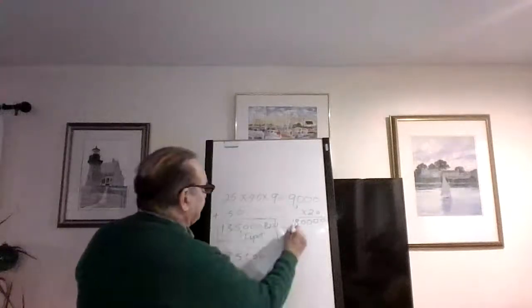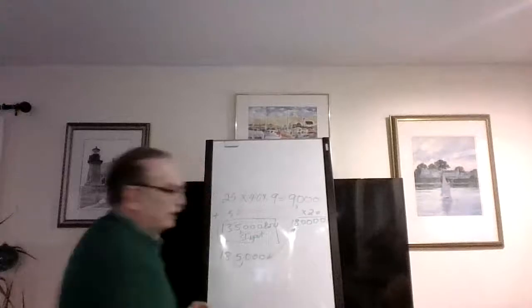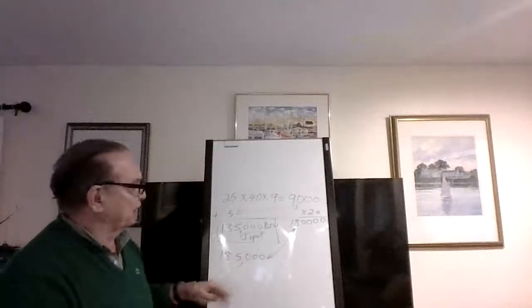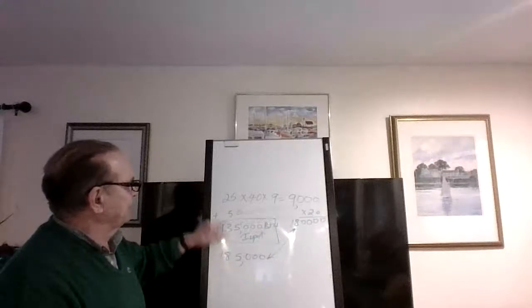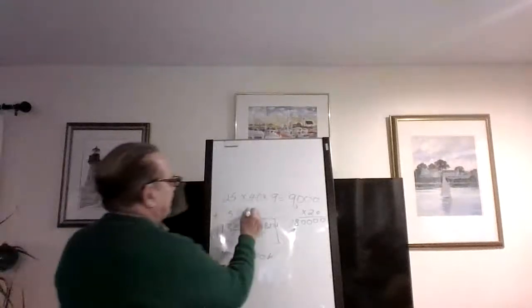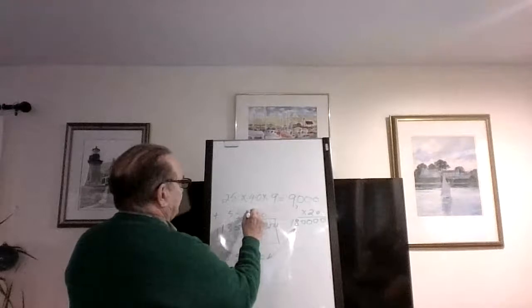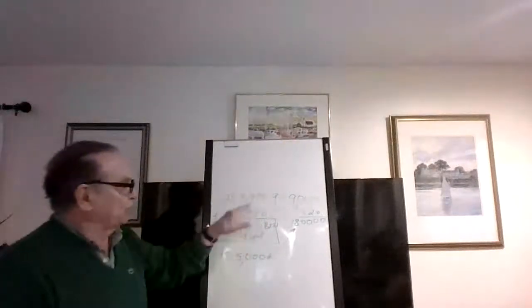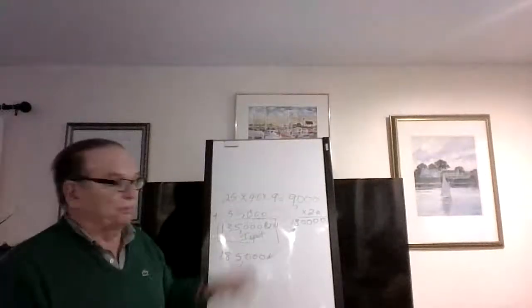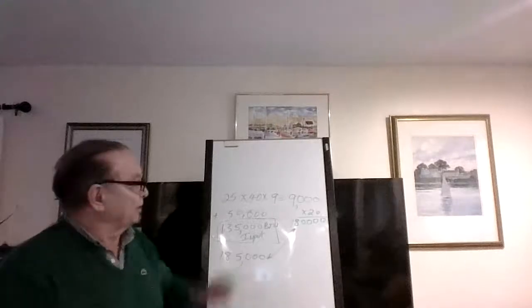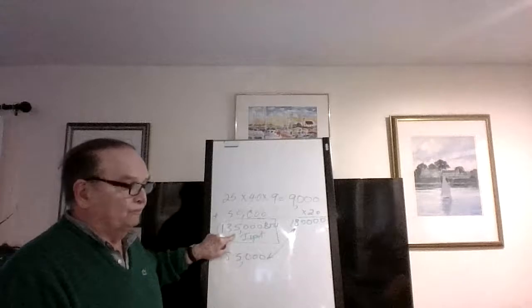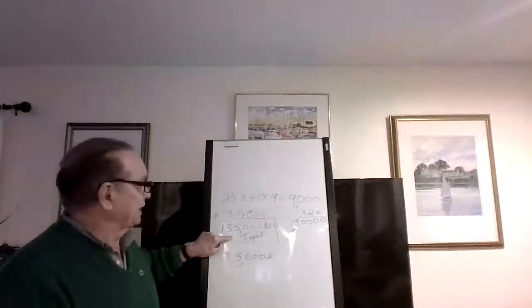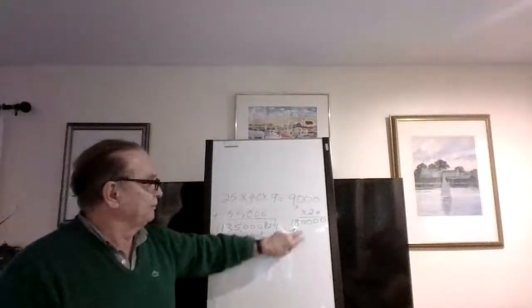Now, most guys aren't going to bother. Close enough. Nobody's going to get too excited. These two, yeah, they'll be on occasionally together, the water heater and the boiler, but not that much. But if these numbers weren't close, you really should put in a fan in the can. Okay. Now remember, I went with a big cellar, and that's not a big boiler, about average, I guess. So that's how you do it.